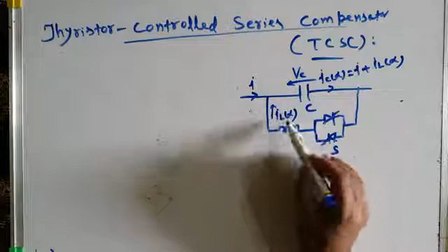Therefore, by alpha control of this thyristor controlled reactor, TCR, by controlling its inductive current, and hence its reactance, with the help of alpha control, delay angle control, we can make it a variable capacitor. Its capacitive reactance can be made higher than the normal capacitive reactance, because this L and C are basically a parallel LC circuit. By controlling the magnitude of current through this TCR, and hence the TCR reactance, we can make the capacitive reactance higher, or we can make it lower. We can make it a variable capacitive reactance.